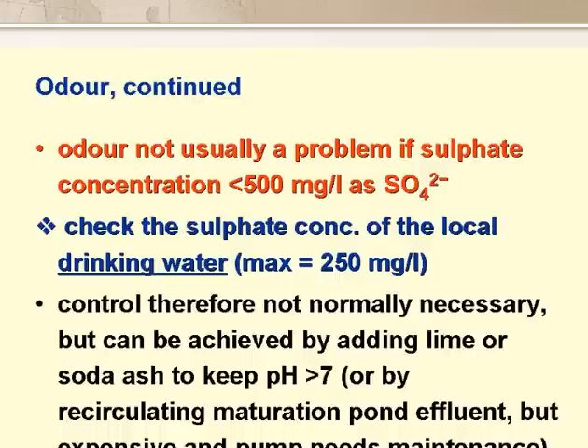Early work in the US showed that anaerobic ponds did not have an odour problem if the sulphate concentration in the raw wastewater was less than 500 mg sulphate per litre. This is quite high, especially as the maximum concentration permitted in drinking water is 250 mg sulphate per litre. The sulphate concentration in wastewater is higher than in drinking water, as detergents, for example, can contain up to 40% by weight of sodium sulphate. Control should not normally be necessary, but if it is required, you can add lime or soda ash to keep the pH above 7.